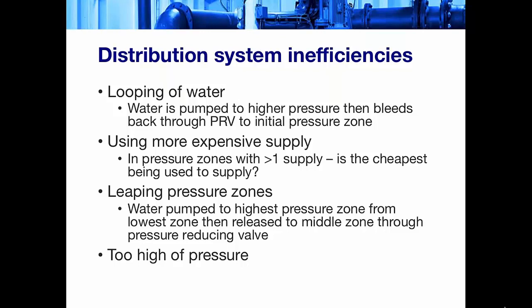We also see sometimes that pressure zones are being quote-unquote leaped. So basically, let's imagine a 3 pressure zone system. Water is pumped from the lowest pressure zone to the highest pressure zone, and then the middle pressure zone is supplied with pressure reducing valves from the highest pressure zone. To make this scenario more efficient, you would have water being pumped from the lower to the middle pressure zone. Therefore, you're not over pressurizing the water only to bleed off that pressure with a pressure reducing valve later on.